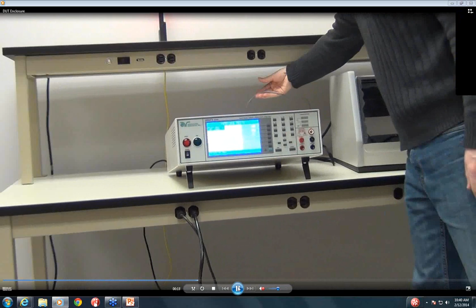So we'll see here, I'm going to start the test, but mid-test, about 3 seconds in, I'm going to open the DUT enclosure door. Right there, the unit says, hey, your door's open, I'm stopping the test. So even by the time I open that door and try to touch the DUT, as fast as I could, this particular HiPot tester is going to discharge within 0.2 seconds. It discharges really quick—it doesn't give me enough time, mitigating the shock hazard greatly.